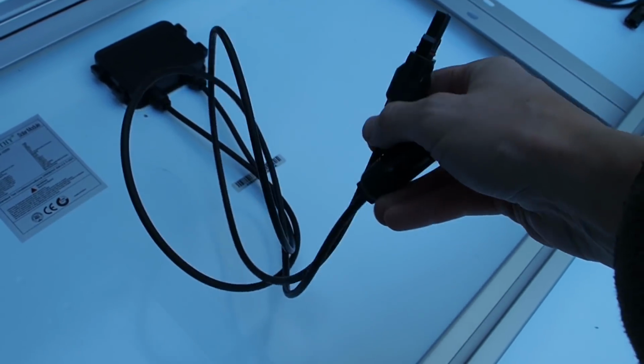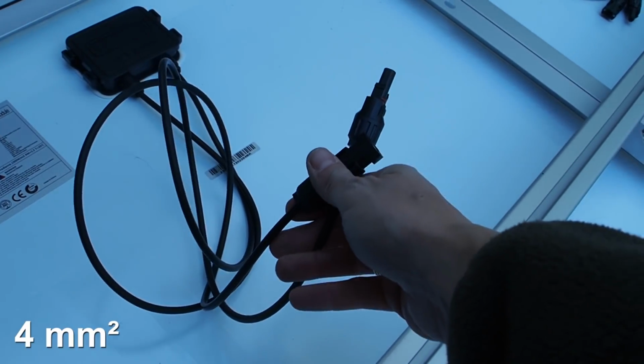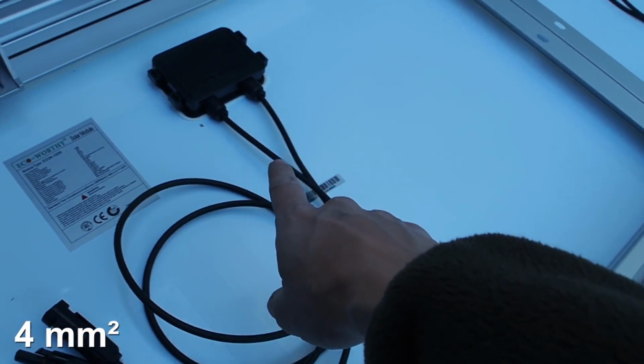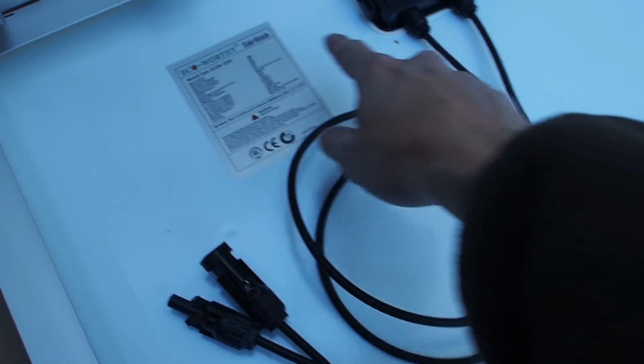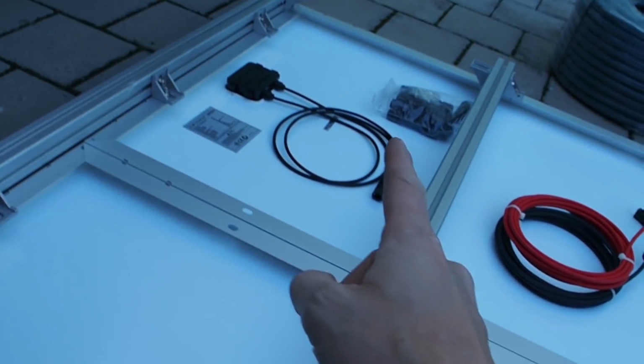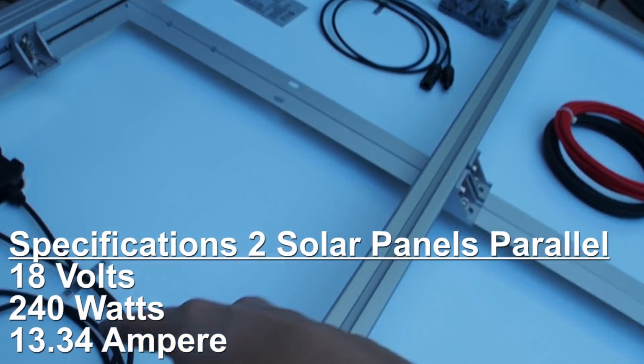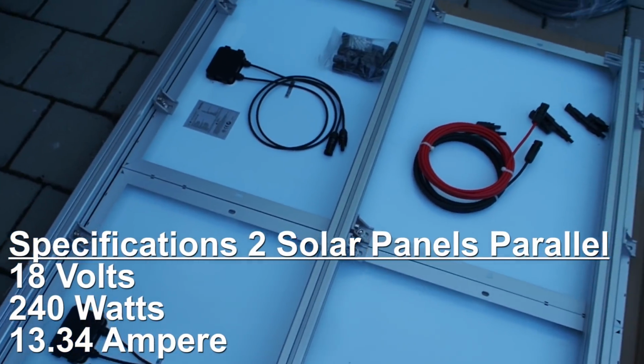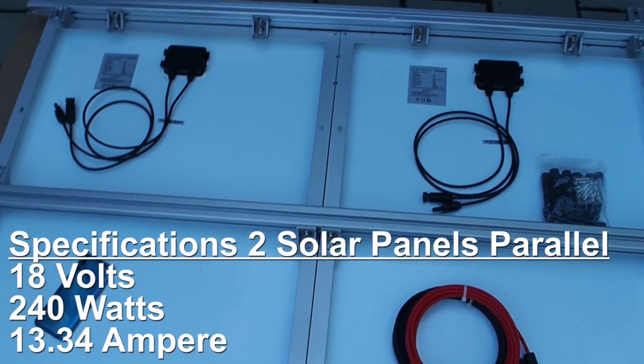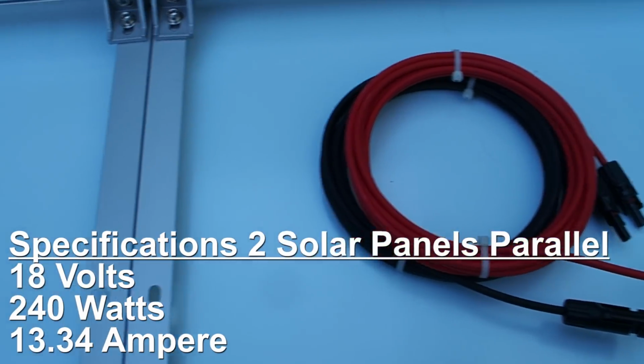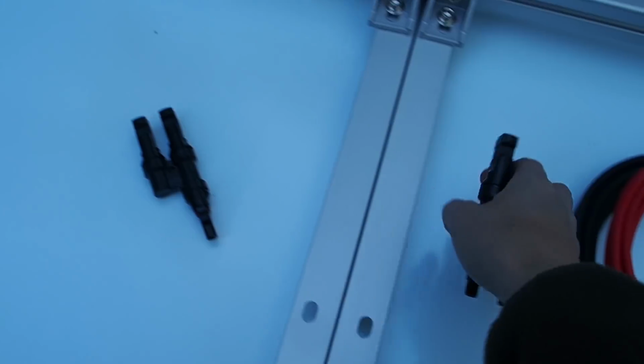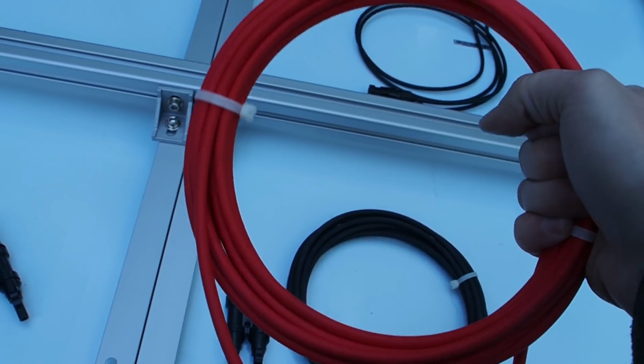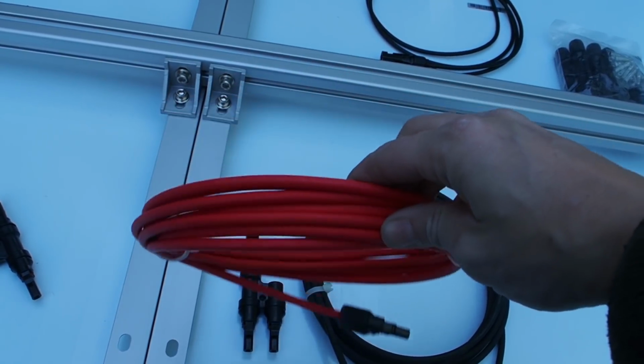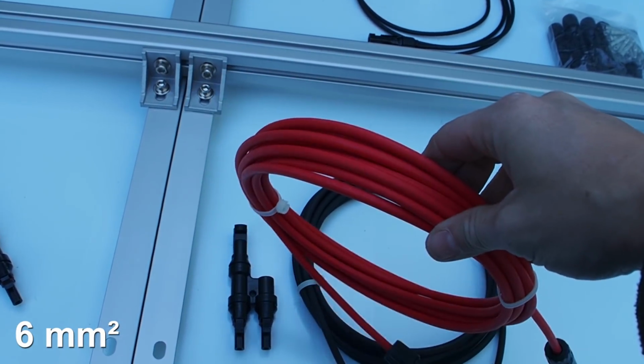Now the cable that comes with one solar panel has a thickness of 4 square millimeters, which is fine for 6.67 amperes, but I'm going to connect these two panels in parallel, so then we have a little bit above 13 amperes. And after the connection, so these are the connectors that I'm going to use. After the connection, I'm going to use a thicker cable, and this has 6 square millimeters.